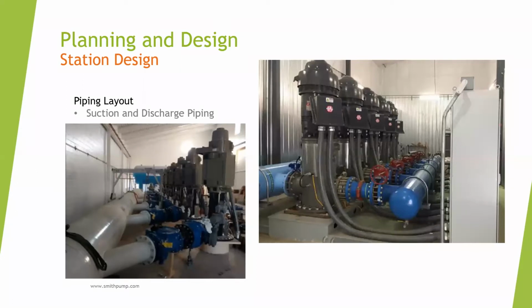Station design and piping layout is important. It determines if the job requires barrel-mounted pumps or wet pit-mounted pumps. Good practice can be correlated to longer pump life and easier maintenance. Let me show you 3 ways poor piping layout can reduce pump life.